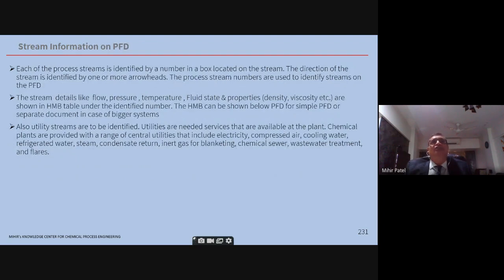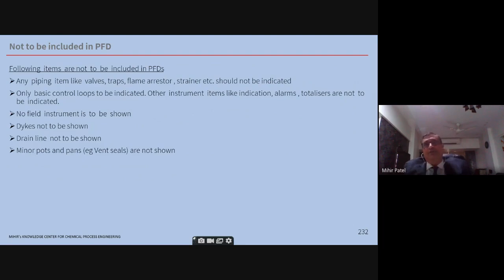Now, the next slide is also very important. What is not shown on the PFD? This is important. Any piping items like valves, traps, strainers are not to be shown. Only basic control loops are shown. Local instruments are not to be shown here. No alarms, no totalizers. No field instruments to be shown. Dikes not to be shown. Drain lines not to be shown. Minor pots and pans. For example, a storage tank has a vent seal. This is not to be shown.